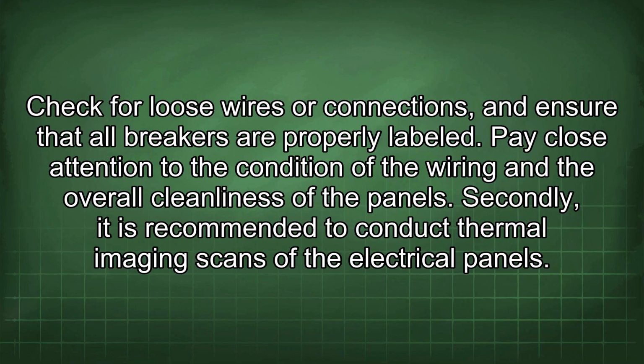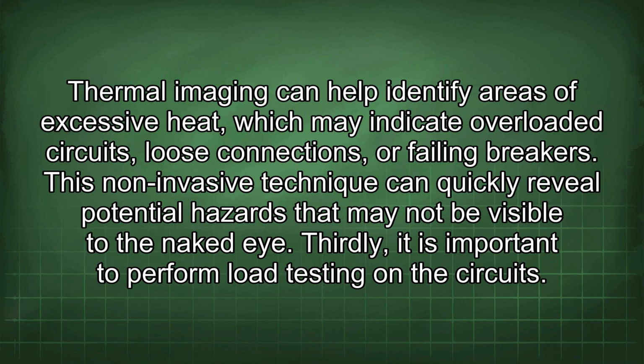Secondly, it is recommended to conduct thermal imaging scans of the electrical panels. Thermal imaging can help identify areas of excessive heat, which may indicate overloaded circuits, loose connections, or failing breakers. This non-invasive technique can quickly reveal potential hazards that may not be visible to the naked eye.